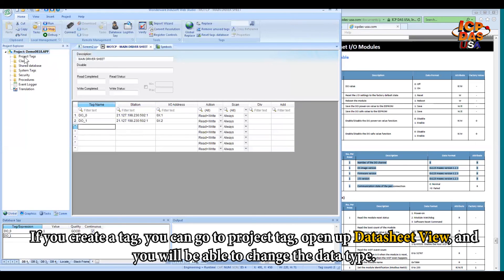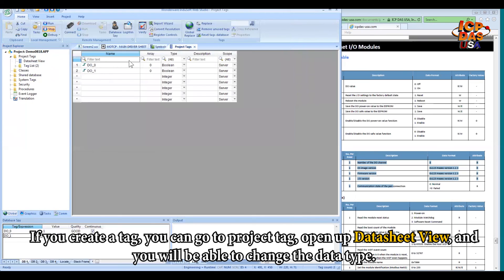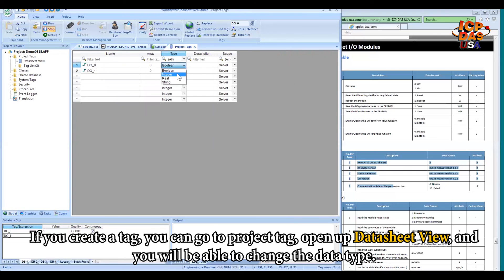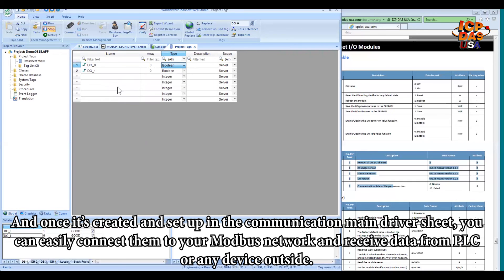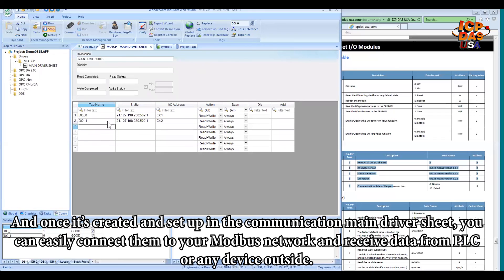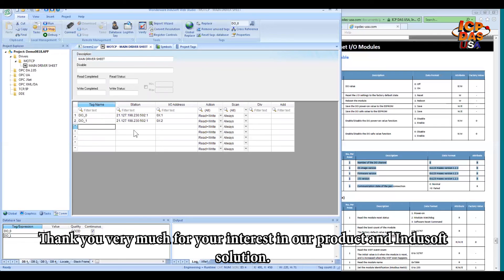You can also go to project tags, tab, and go to open up the datasheet view. And you will be able to change the data type from boolean into integer, real, string. And once it's all created and set up in the communication main driver sheet, you can easily connect them to your Modbus network and receive data from PLC or any device outside. Thank you very much for your interest in InduSoft.